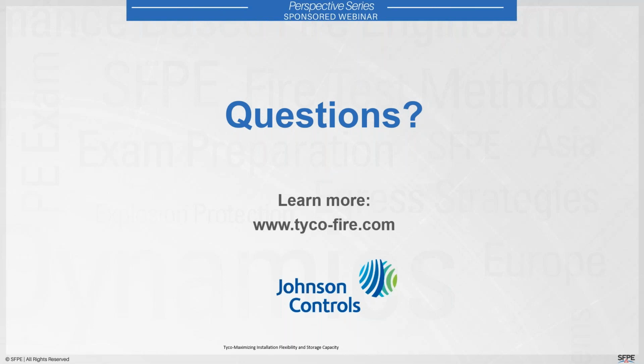they're upright and pendant extended coverage K25.2 sprinklers that are available. They're CMSA type sprinklers. They certainly can be used. My presentation focuses more on the ESFR applications. I believe the K25 EC25s are limited to either 40, 35, I think 35-foot ceilings. I have to go back depending on the commodity classification again. So they might go to 40, I'm sorry, 40 feet, but they certainly don't go as high as ESFR sprinklers.